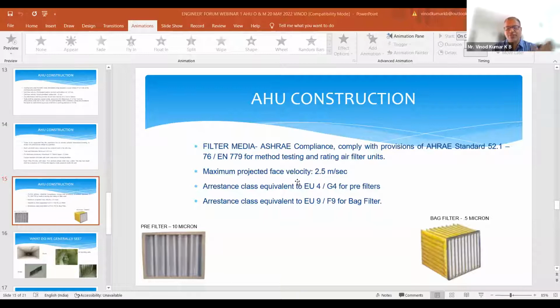Okay. Generally, for continuous use, you will look at a minimum 6-month to 1-year period, based on the kind of usage and the kind of maintenance that you do in your building. Because when you allow the AHU to leak, when you allow dust or other outside air to come into the AHU, then your filters get choked much faster. So there is no literal timing, because if you feel that the pressure level is dropping because the filter is choked, it is time to replace the filters. Only thing is, a pre-filter can be washed, but the other one cannot be washed. The G4 can be washed, not the F9.